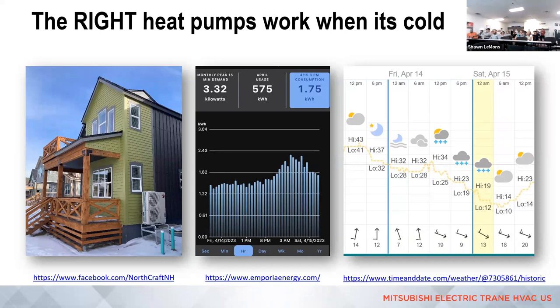But I also want to point out that we're talking certainly less than 2.3 to 2.4 kilowatt hours per hour to heat that house, which isn't that much when you think about it. This system is rated for about 5,500 watts, but it's running at less than half that when it's 10 to 20 degrees outside. So if it can do 50 or 60 degrees worth of work at less than half its capacity, there's plenty left to handle whatever you're throwing at it.